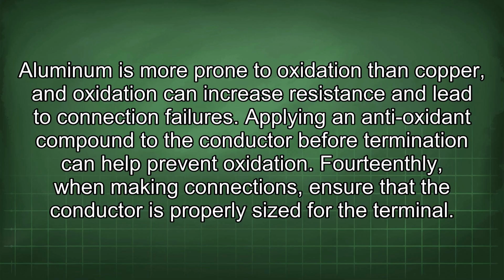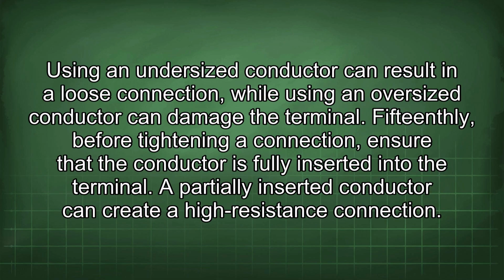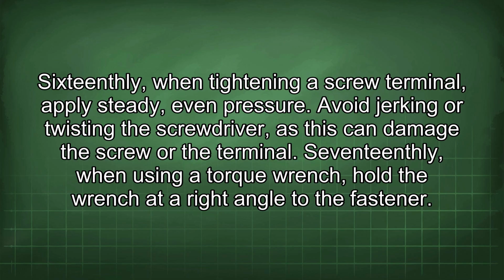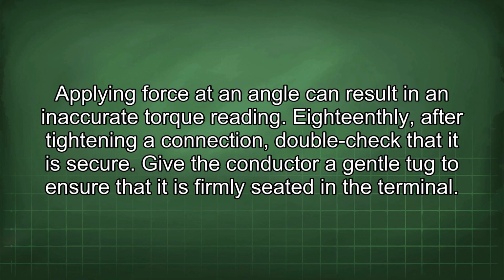Fourteenthly, when making connections, ensure that the conductor is properly sized for the terminal. Using an undersized conductor can result in a loose connection, while using an oversized conductor can damage the terminal. Fifteenthly, before tightening a connection, ensure that the conductor is fully inserted into the terminal. A partially inserted conductor can create a high resistance connection. Sixteenthly, when tightening a screw terminal, apply steady, even pressure. Avoid jerking or twisting the screwdriver, as this can damage the screw or the terminal. Seventeenthly, when using a torque wrench, hold the wrench at a right angle to the fastener. Applying force at an angle can result in an inaccurate torque reading.